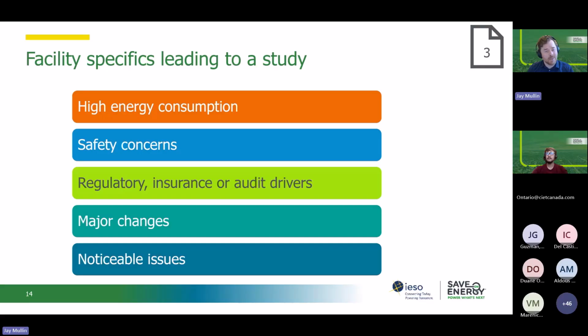Facilities in the range of 25,000 to 100,000 square feet is more that sort of threshold or trigger point where it makes sense to pay more attention to balancing your airflows, especially if you do have that high process exhaust. So thinking like greater than 15,000 CFM, if you have multiple exhaust types, multiple makeup air sources, a more complicated system. Another rule of thumb that's often used is your air changeovers. So if you have more than 1.5 air changeovers per hour, there's probably a lot of energy going into that.